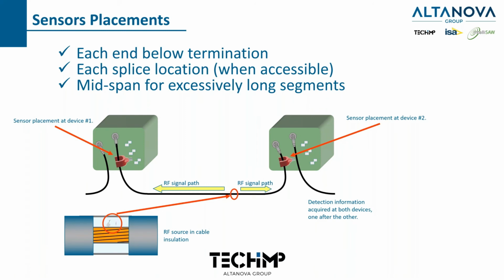Now this graphic is exactly the same thing I just talked about, only it's in a pad mount utility type situation. Same thing though, just below the termination, you put the sensor. If there's a splice here, we'll do it on each side of the splice, and then we'll move to the next test point.